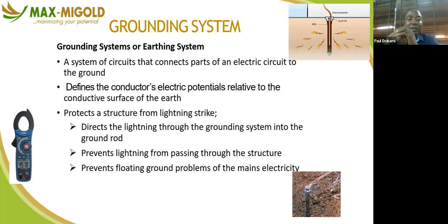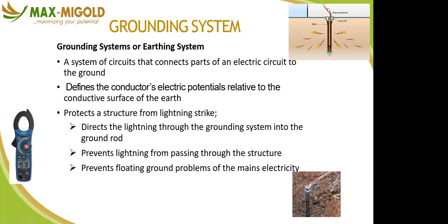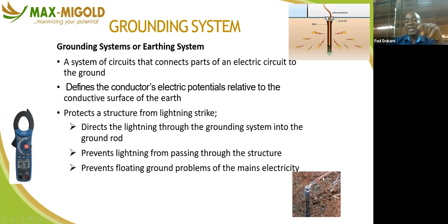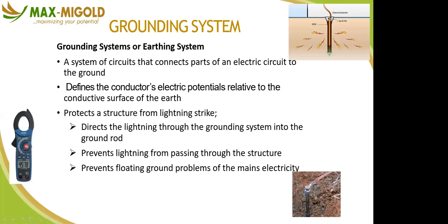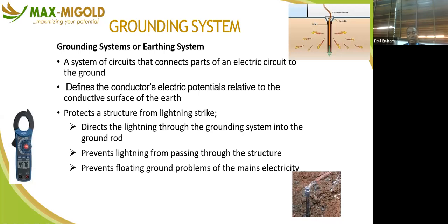So when you are carrying out earthing, what is earthing? Earthing is a system of circuit that connects part of an electric circuit to the ground. We have the earth rod and the wire. In some installations, you have that green cable, that green conductor. It's connected to the DB straight to the earth rod. The earth rod is buried. It's like this earth rod here. It's buried in the ground, and this is the cable that is coming. It's tied to it. If there's any leakage current, this is the cable coming, this is the earth rod. Any form of surge or rising current flows through that earth conductor to the ground via the earth rod.